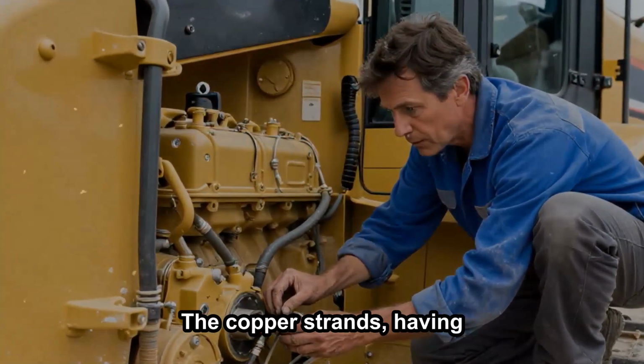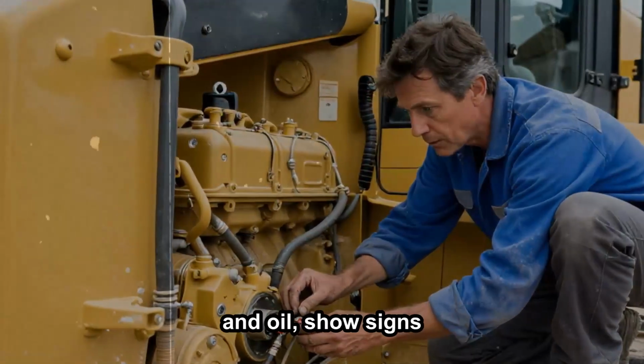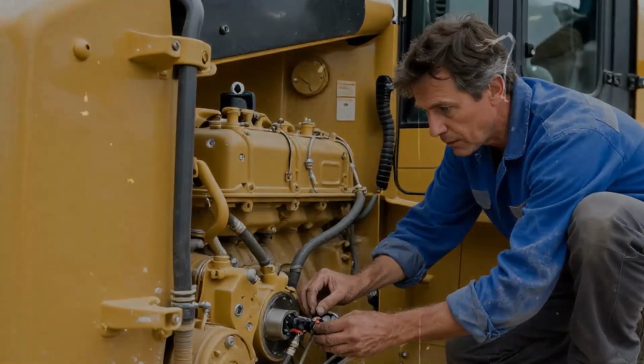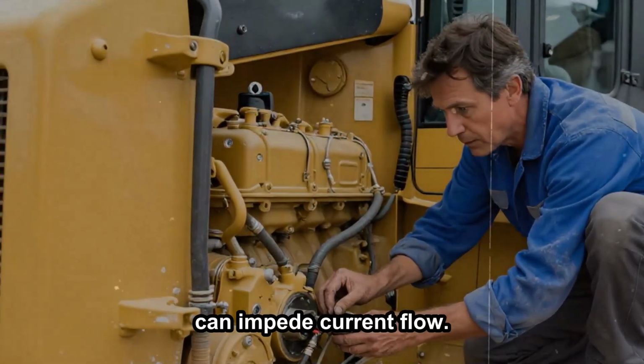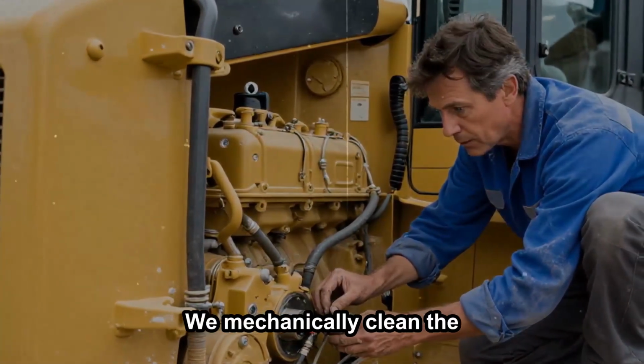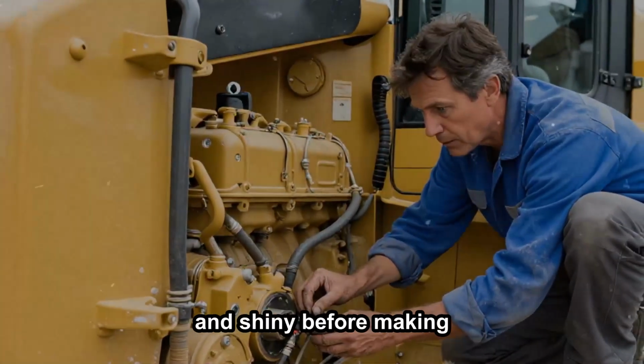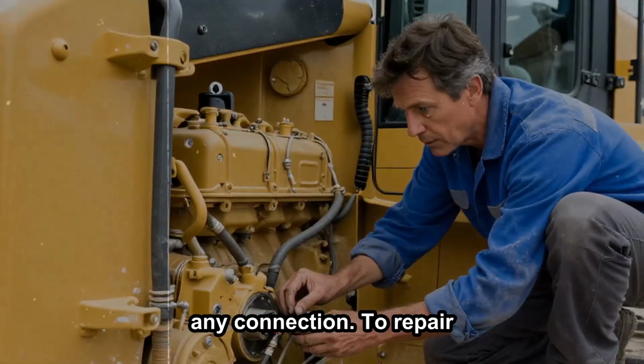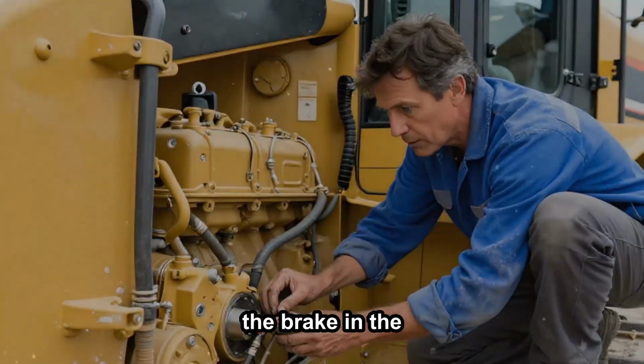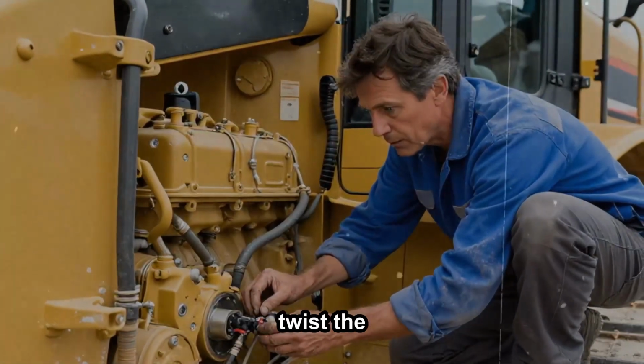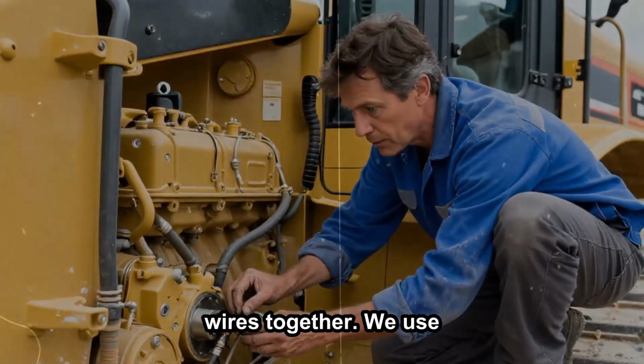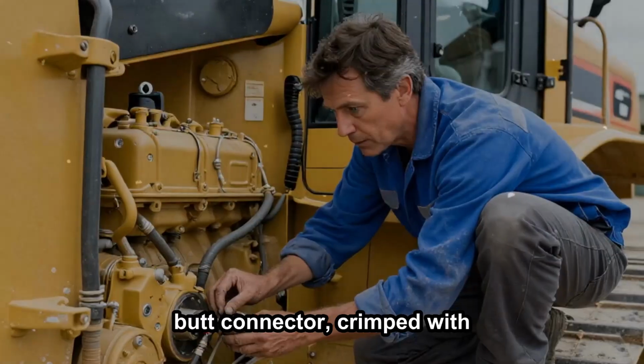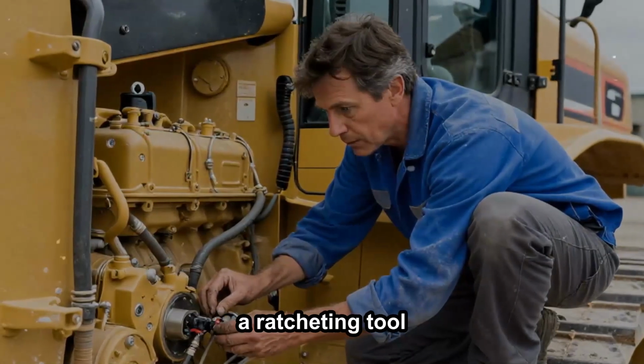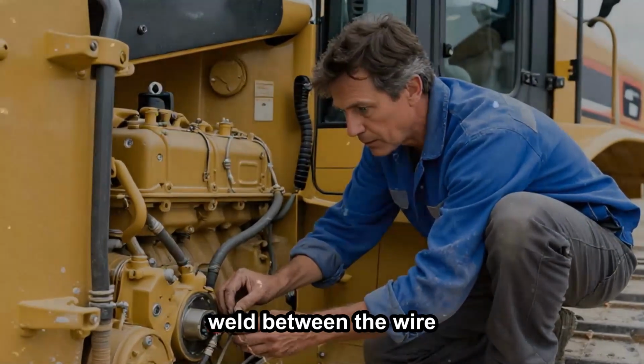The copper strands, having been exposed to air and oil, show signs of oxidation, a dull tarnish that can impede current flow. We mechanically clean the strands until they are bright and shiny before making any connection. To repair the break in the copper, we don't just twist the wires together.